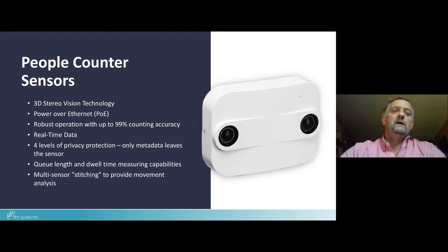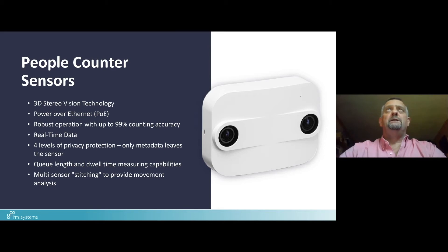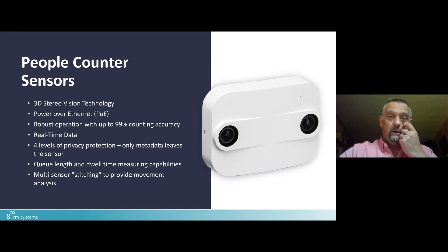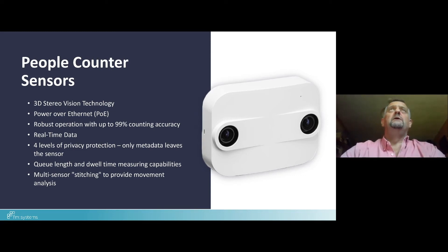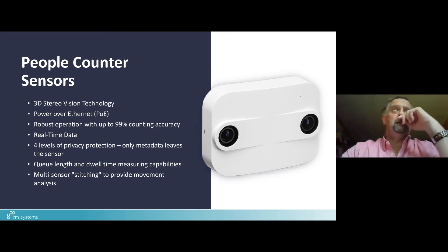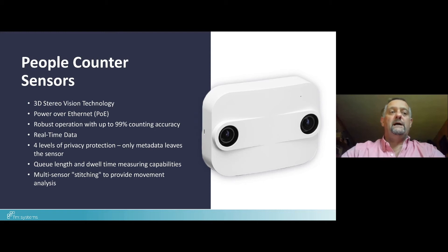These sensors are slightly different to the open area sensors and PIR sensors discussed earlier. They use 3D stereo vision technology — camera-based technology. Similar to the XY Sense sensor, privacy is of paramount importance; only metadata leaves the sensor, with no imagery leaving it. There are up to four levels of privacy protection built in. They are also intelligent enough to count bi-directionally, understanding a person walking in and walking out of a space.